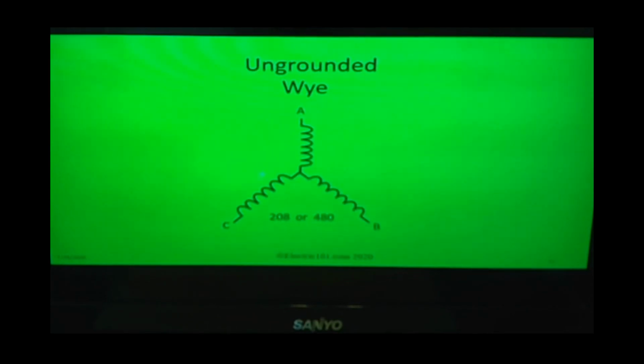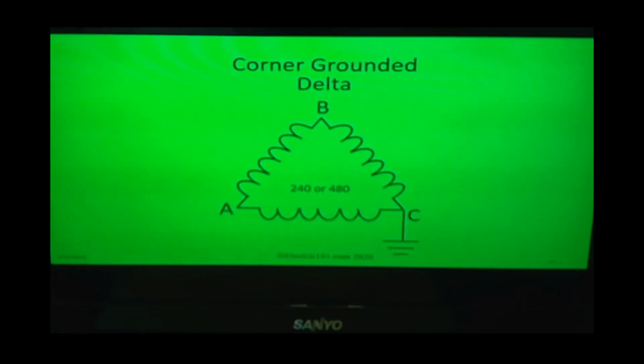Now I could have an ungrounded Y system too. Now again, you're only going to have one voltage. That transformer will put out either 208 volts or it'll put out 480. Because there's nothing connected to the neutral point, there is no neutral wire. So I take my measurements between A and C, you get the 480. A and B, 480. C and B, 480. Okay, and if we're using a 208 volt three phase ungrounded, then all these measurements should be 208. So there are different types of transformer configurations.